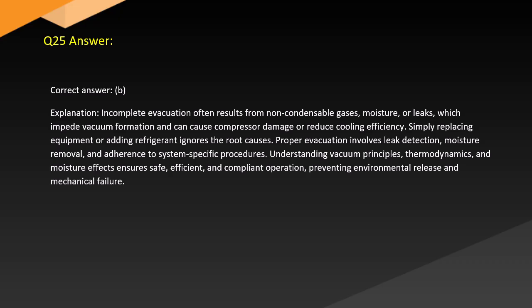reduce cooling efficiency. Simply replacing equipment or adding refrigerant ignores the root causes. Proper evacuation involves leak detection, moisture removal, and adherence to system-specific procedures. Understanding vacuum principles, thermodynamics, and moisture effects ensures safe, efficient, and compliant operation, preventing environmental release and mechanical failure.